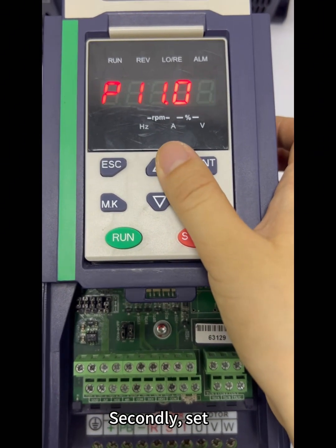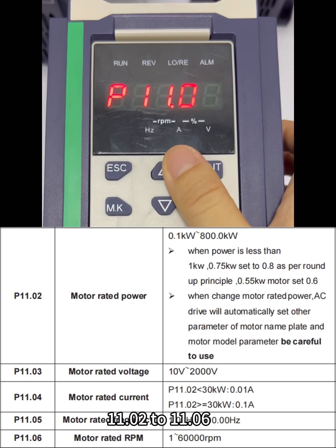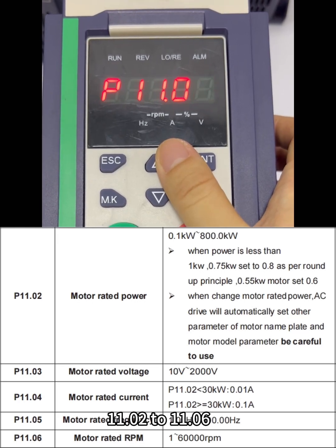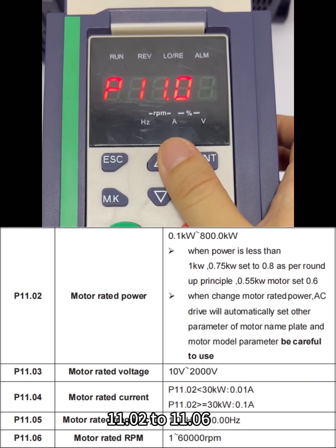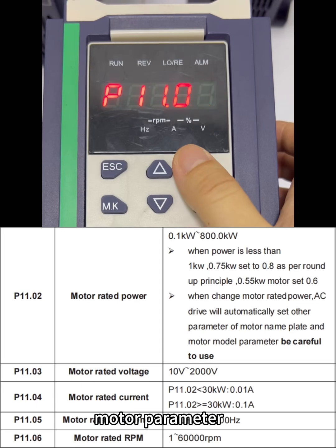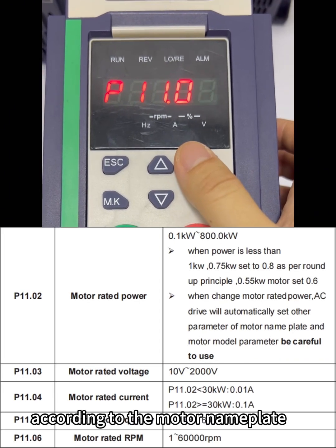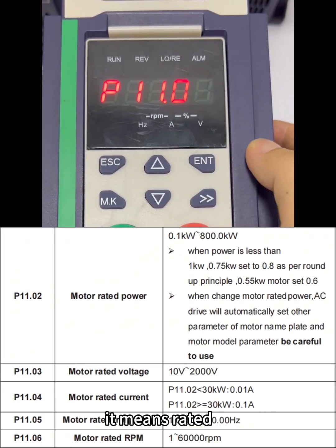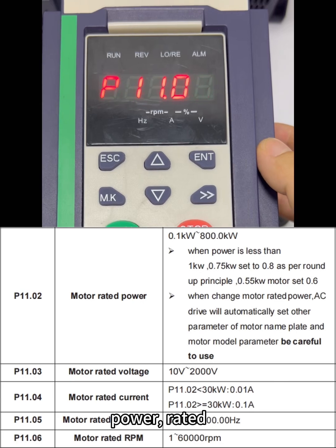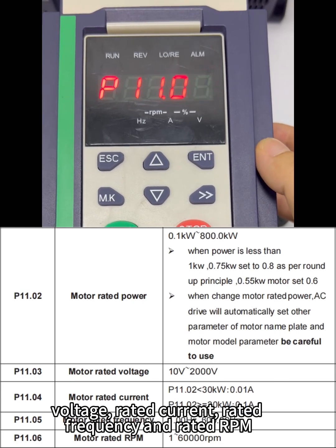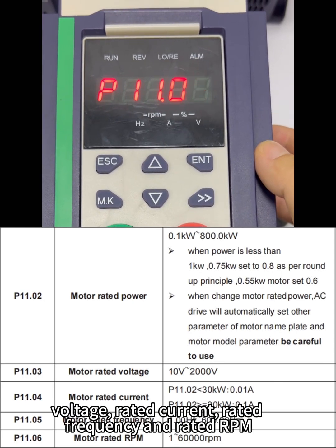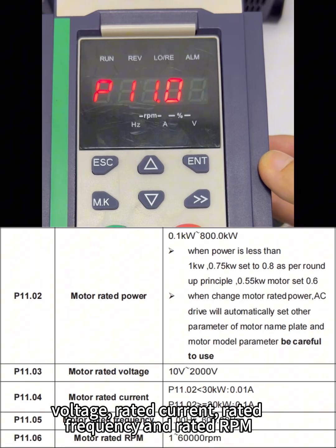Secondly, set 11.02 to 11.06 motor parameter according to the motor nameplate. It means rate power, rate voltage, rate current, rate frequency, and rate RPM.